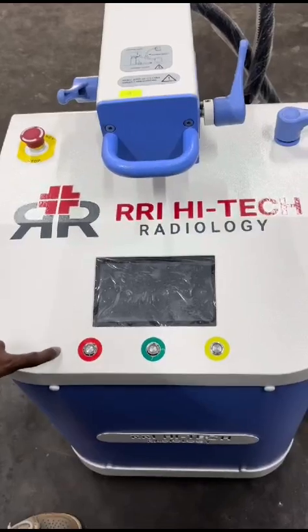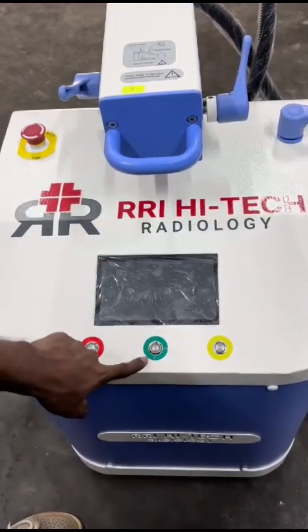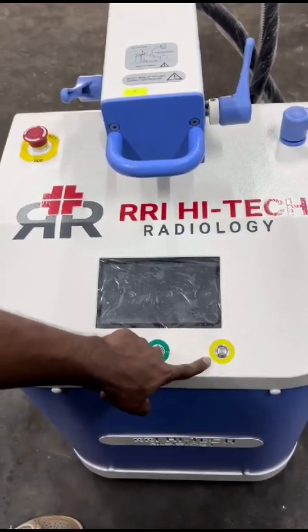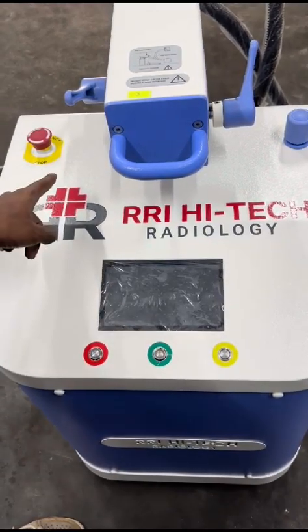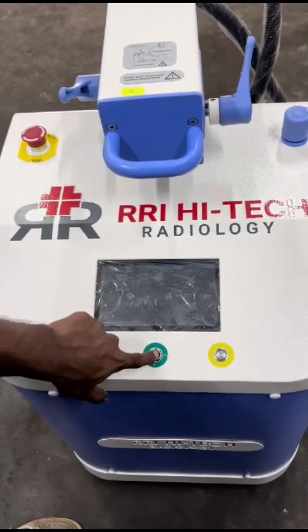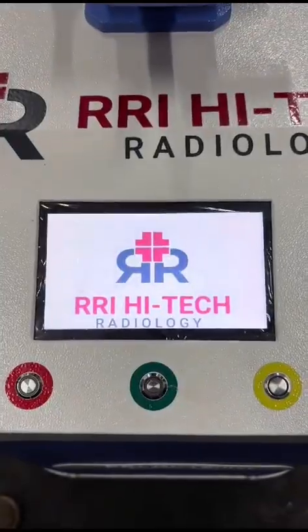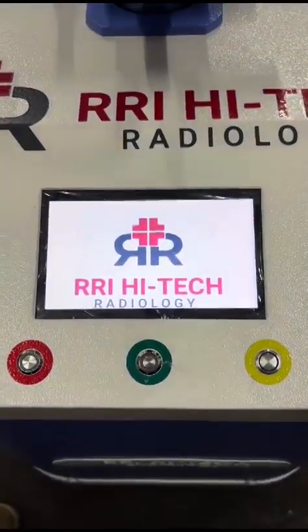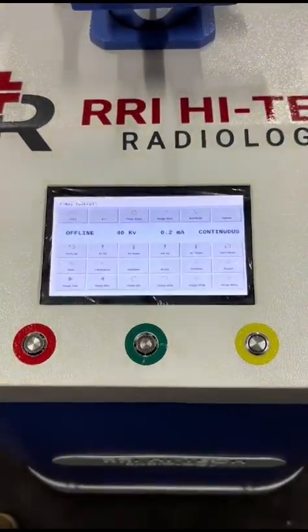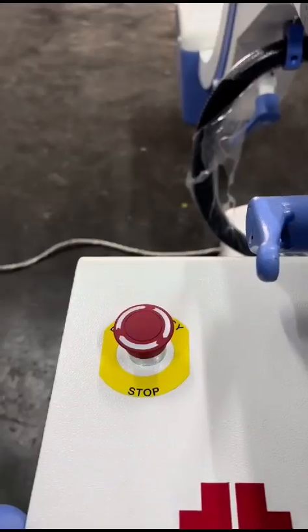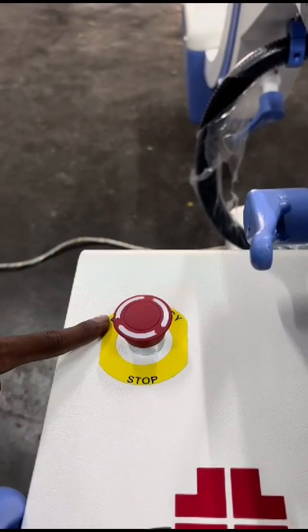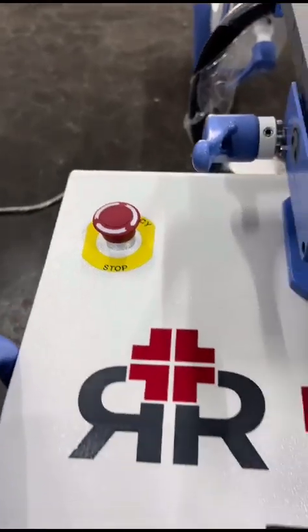The red switch is for turning off, green switch is to turn on the machine, and yellow is for exposure. After connecting the power cord, click on the green button to turn on the machine. Wait for 50 seconds for the machine to boot up. Here is the emergency stop. In case any failure occurs, you can click on it.